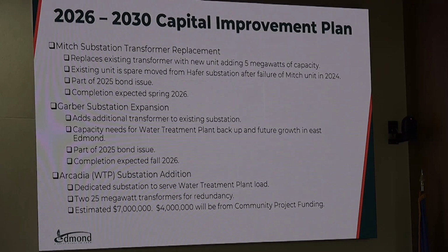One of the new substations is the Arcadia substation - I called it the Arcadia substation, I don't know if we need to vote on this or not - but that will be a dedicated substation for the water treatment plant. When they have all three phases completed, they're going to have about 19 megawatts of load out there. One of our substation transformers serves about 25 megawatts. We plan to put in 2 transformers there for some additional redundancy, using that to serve some of the load in East Edmond, but primarily it will be a backup for the water treatment plant. We estimate that one at about $7 million currently.